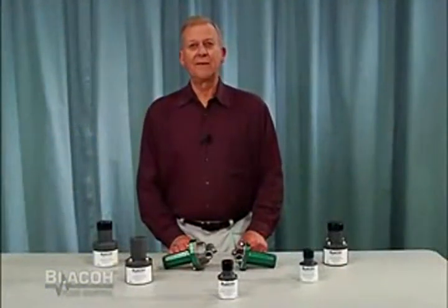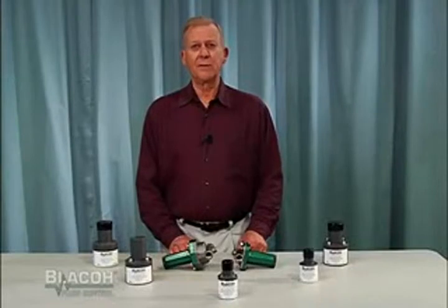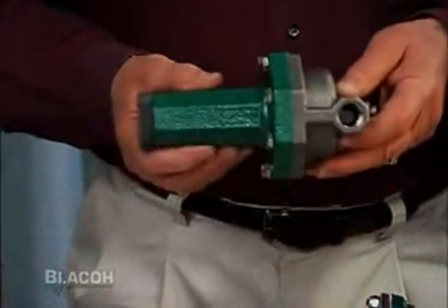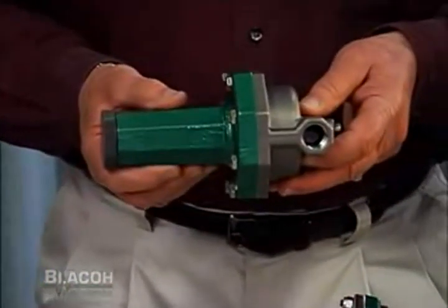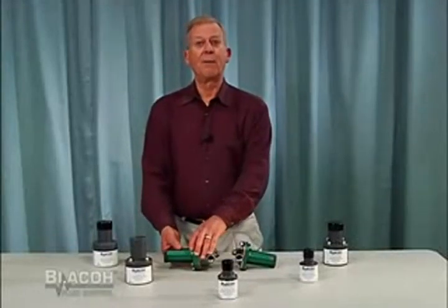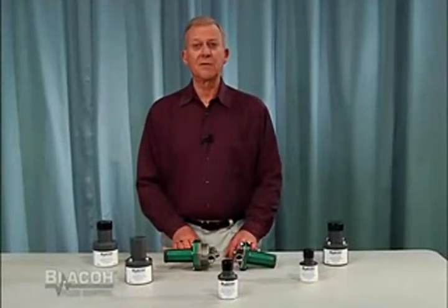Blacoh offers a complete line of back pressure and pressure relief valves. Back pressure valves are generally used to create pressure resistance at the discharge of a reciprocating pump. There are several reasons why a back pressure valve is used. One of the common reasons is to create a back force to help positively seat the pump's discharge ball valves.